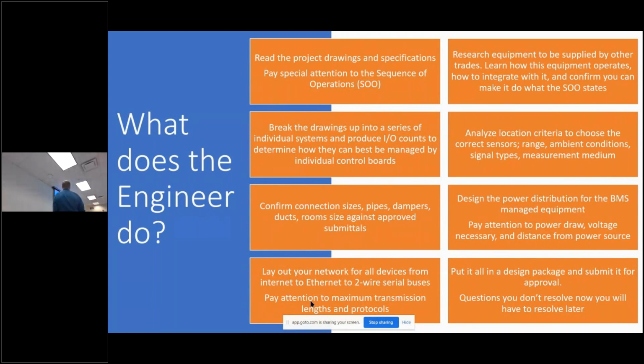So after you read the project drawings, you've got to break up your drawings into a series of individual systems. You have to look at air handlers and pump systems and try to determine, what's my I/O count? What's my input output count?